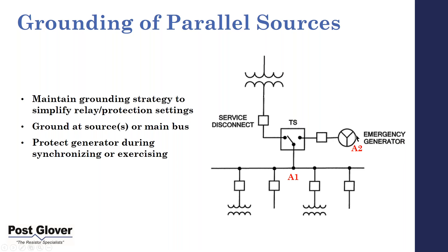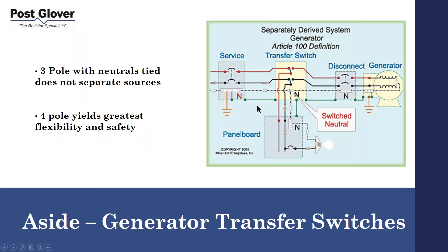In terms of three-pole versus four-pole transfer switches: with a four-pole switch, you're also switching the neutral, which makes everything clean — you have multiple HRG protections on both sides. With a three-pole switch, your sources are not separated, so even if your generator is off, the neutral is still tied to the transformer. That means you don't want to be working on that generator while the transformer is live. The four-pole approach is the recommended configuration.